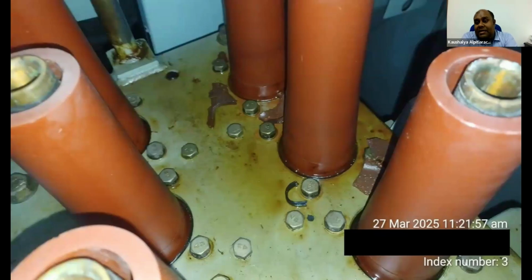These images show some contamination of this copper tubing, dust contamination. Just see the level of dust there on your insulators and on your bus bars. That will bring up your pollution degree from level 2 to level 3. If your humidity is not controlled, then you are definitely going to have issues there at your installation, which will lead to voltage tracking and later on will develop partial discharges.